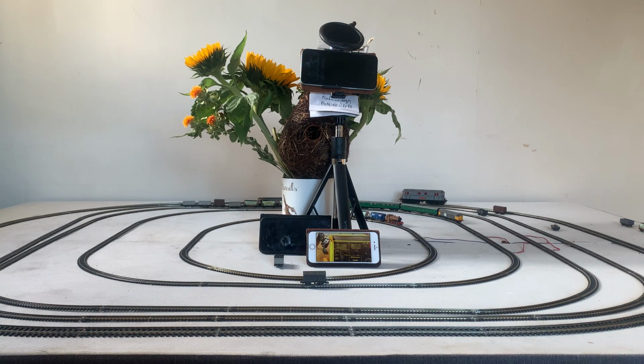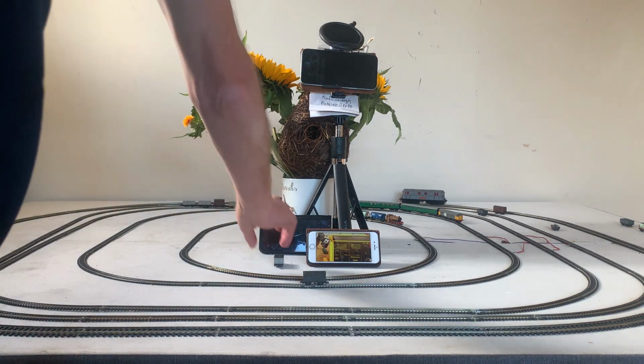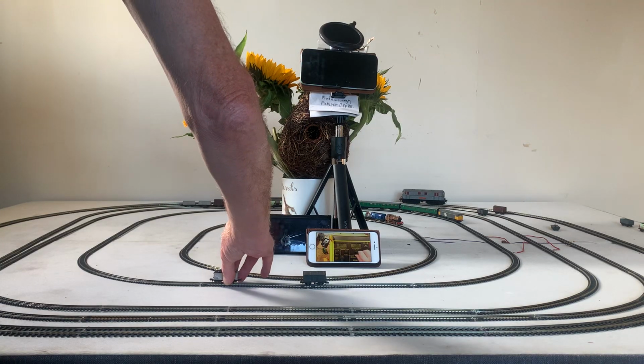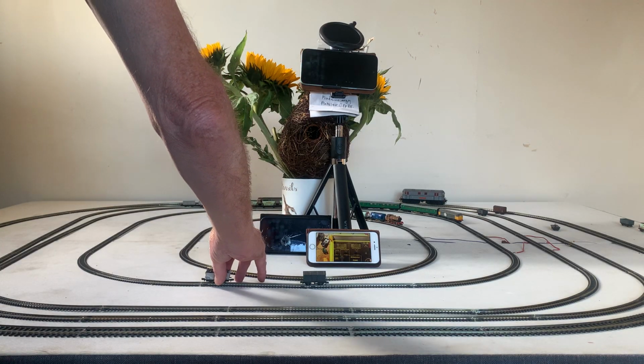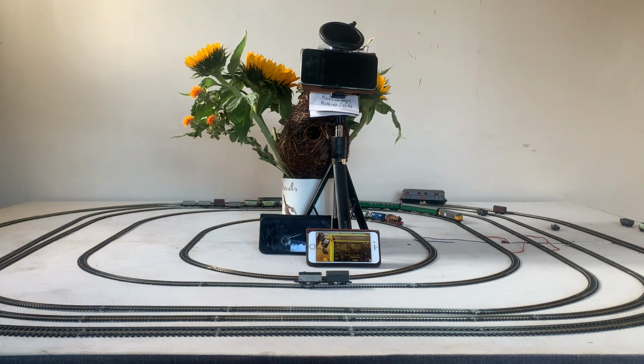I'm guessing that if it tripped, that is arcing across, but it's doing so at 3,450 volts, which is reasonable enough. And just out of interest, what happens if I bump it straight back up to 2,000 again and just leave it sitting there for a while? I want to set it way up too high. Still getting used to this thing. I've been over greedy again. If you set it to 2,000 volts, as soon as you exceed the 2,000 volt test, it won't let you go any higher, and it cuts it off to 0. So it's still holding up.